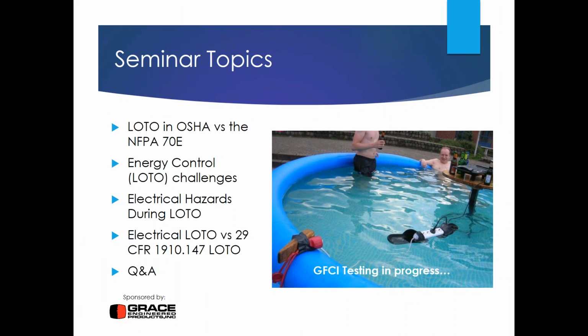In terms of what we're going to cover, we're going to talk about the differences between lockout, tagout, and the OSHA standards versus the NFPA 70E. There are some differences that we want to cover, and of course, how OSHA would normally have you manage any hazard is to follow whatever standard provides the most restrictive protections. In some cases the 70E has additional precautions that OSHA does not, and the reverse is also true. OSHA occasionally has some things that are not in the 70E. With that said, when you're applying the standards, always know all the standards that might apply and then follow the most restrictive of them.